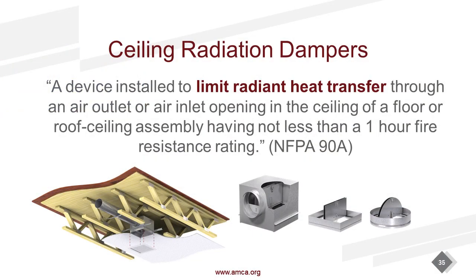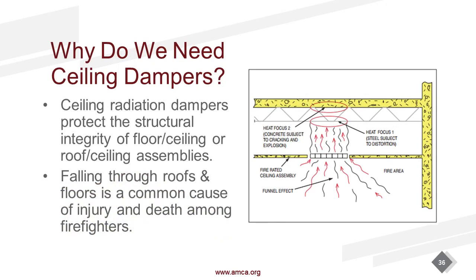Ceiling radiation dampers, we're just going to touch on them for a second because we're going to talk about that for an hour at 3 o'clock. They limit radiant heat transfer. That's their only job. Not fire, not smoke, heat. They're very concerned with the transfer of heat. They protect the structural integrity of the structure above them. So think of your high-rise and low-rise multifamily, dorms, smaller hotels, motels, things of that nature.